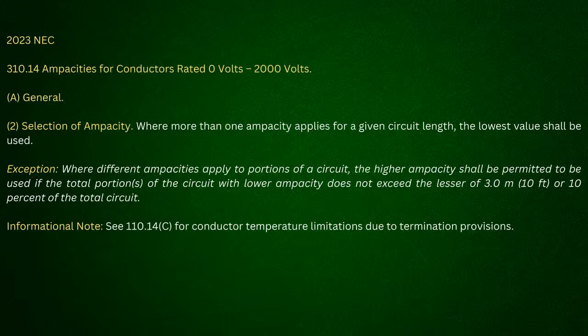No, it doesn't. And then just to finish it off, I got a sleeve. I could look at the exception here, and it says where different ampacities apply to portions of a circuit, the higher ampacity shall be permitted to be used if the total portions of the circuit with lower ampacity does not exceed 10 foot or 10% of the total circuit. So I could look at it that way. I've got a 100-foot run and 10 foot or less of a sleeve. I could use it this way if I wanted to, just to keep you from arguing with me.